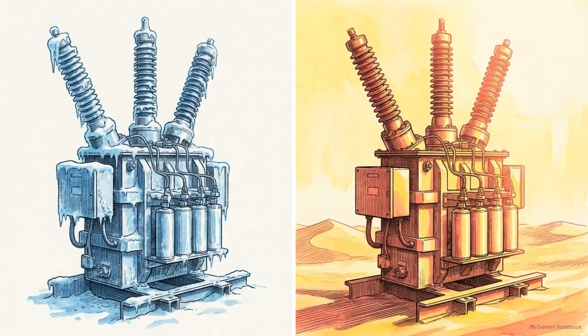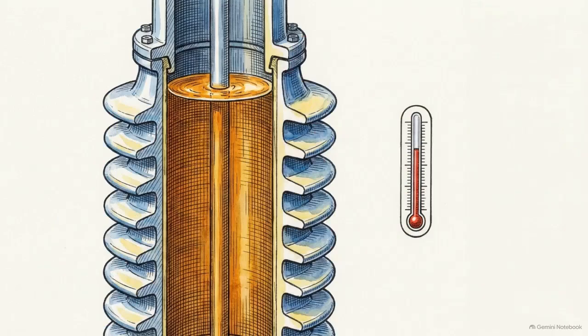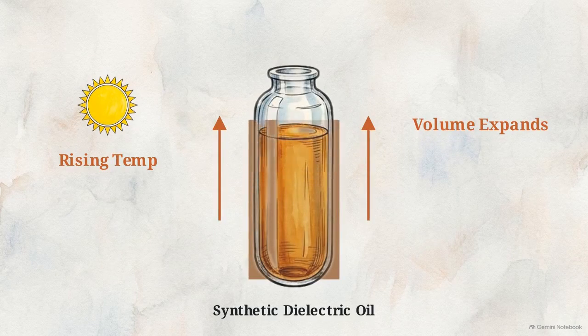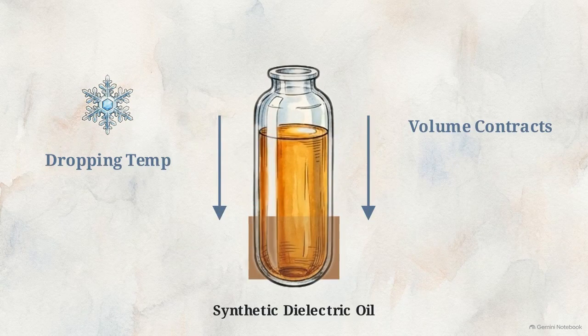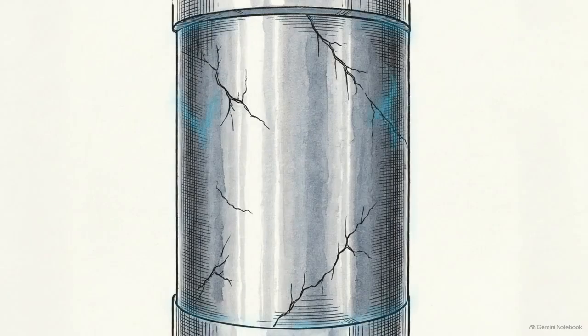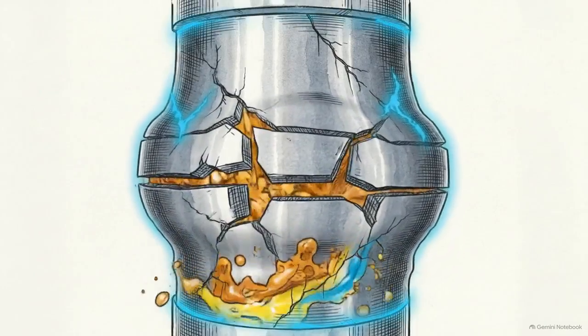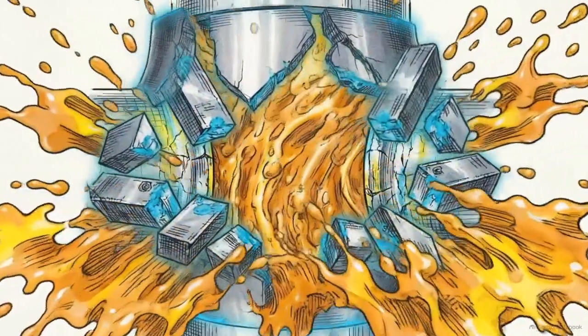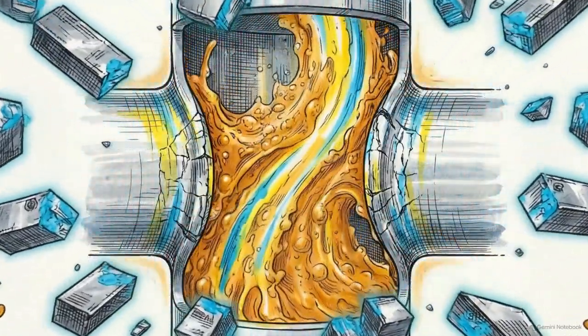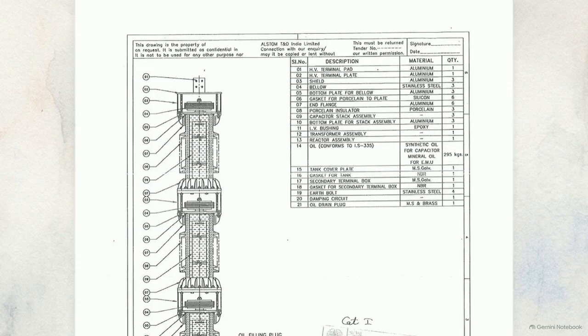Beyond electrical accuracy, these units must survive outdoors in highly exposed substations, where temperatures can swing from freezing winters to blistering summers. The entire hollow cavity of the CVT is filled with synthetic dielectric oil to insulate the components. When ambient temperatures rise, that liquid oil expands. When they drop, the oil contracts. If you completely seal a rigid, fluid-filled chamber and heat it, the thermal expansion creates internal pressure, which would eventually fracture the porcelain tower. To prevent bursting, the design incorporates an expansion system at the top, a stainless steel bellows.